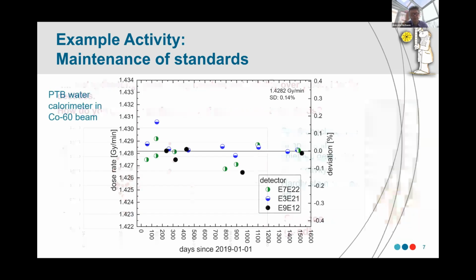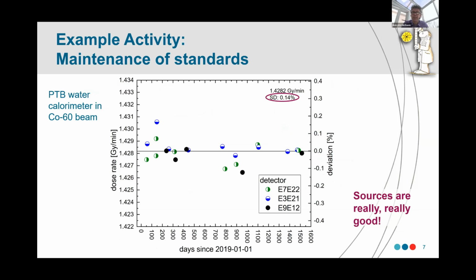Another example, this was provided to me by Ralph Peter Kapsch from PTB, and this is the performance of their water calorimeter in their cobalt-60 beam. So water calorimetry is their primary standard, as it is a number of NMIs for absorbed dose to water. And what this shows with 3 different detectors, they're able to monitor the performance again at an uncertainty of around 0.1%, which is really, really useful. And sources are really, really good. So it's not under question how good radiation sources are for providing the stability that we need for our measurements.